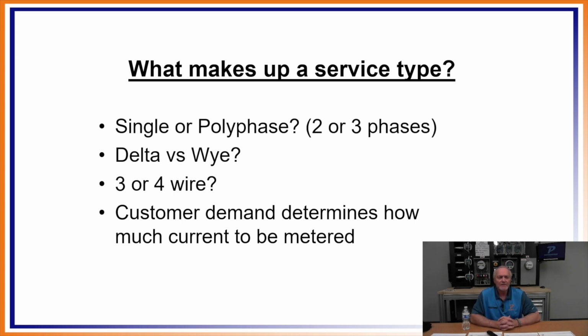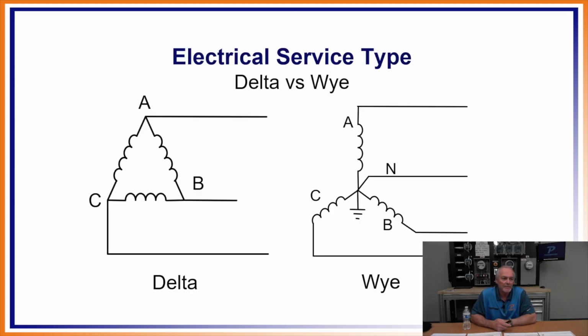What makes up a service type? Okay, you've got single or polyphase, right? So 2 or 3 phases, a delta versus a Y, and then a 3 or 4 wire, and then the customer demand determines how much current is to be metered, right? So depending on the site, how much load is at that site, and how much current they need, that's definitely going to affect it. Because you're going to see here in a second, they fall into categories very quickly of how much current that meter can take. So if it falls above that, then you have to go to a different meter, right? And we're going to see all that here in a second.